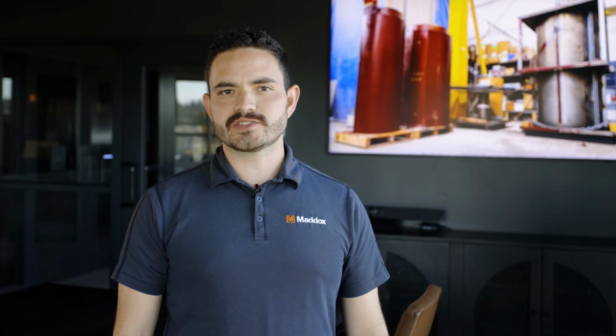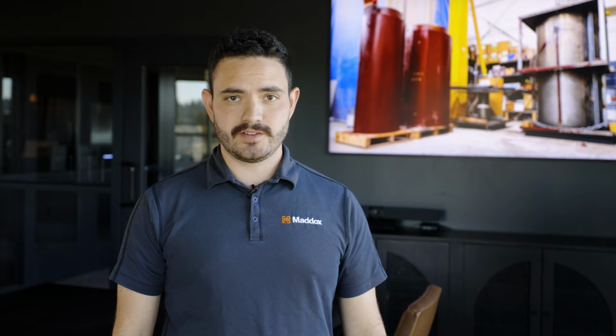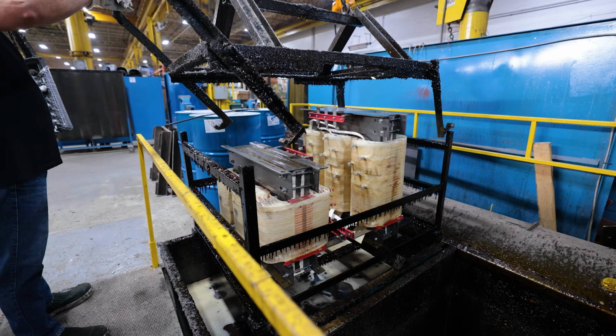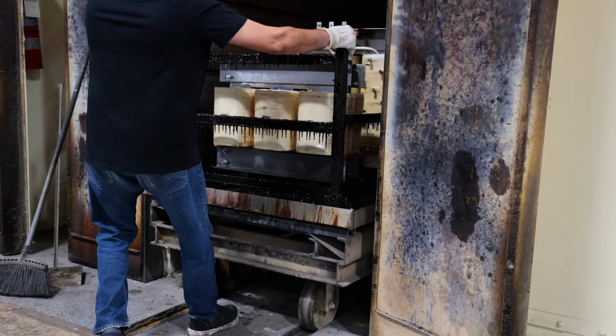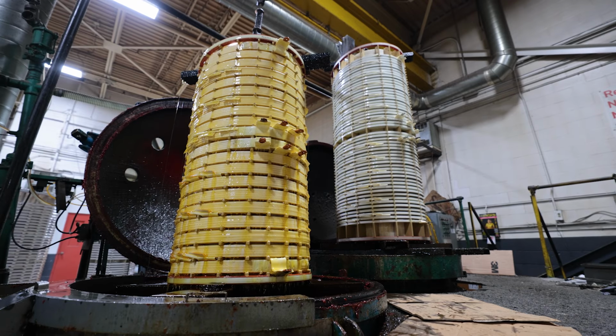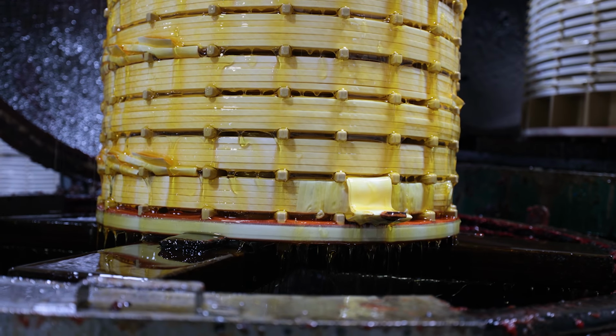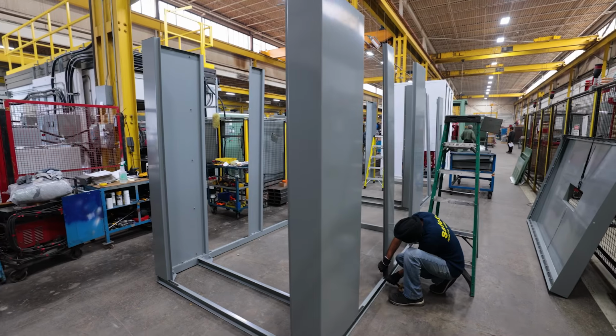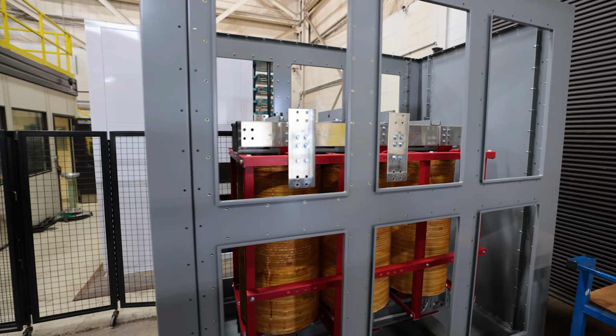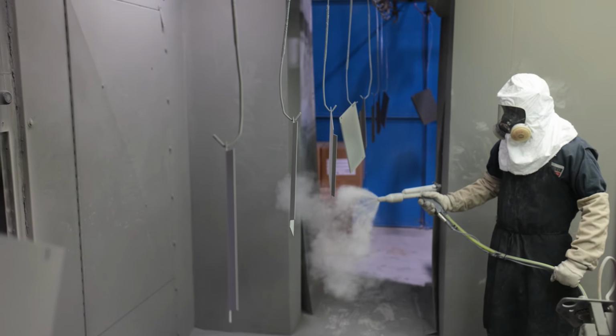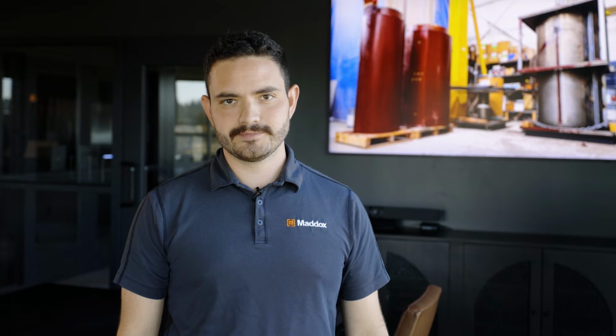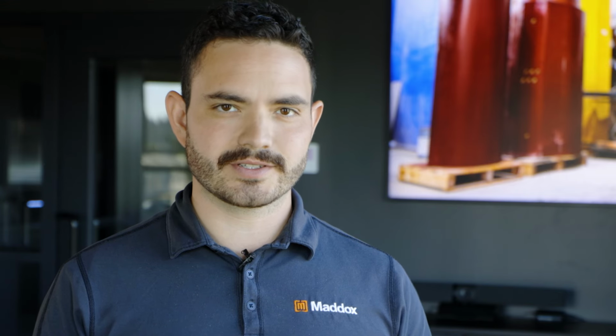So most dry type transformers have a few basic protective features. The default winding protection is VPI, or vacuum pressure impregnation, where the windings are coated in a high temperature polyester varnish, and the unit is typically inside a steel enclosure coated in an anti-rust paint. For some environments, this basic protection isn't enough. Cast resin transformers are built for such conditions.